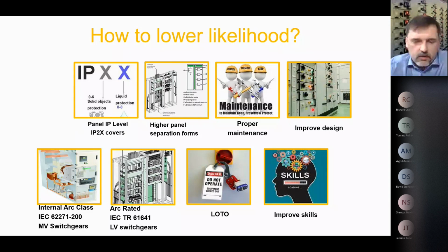You might improve your design. And by improved design, I mean the design of your system. So when you are in the design phase, of course, not every configuration of your system is effective, especially for safety. So you might work with this a bit more. But as well as a hardware design of the panel itself. For the panels, when we talk about the switchgears, we might have internal arc classified switchgear for medium voltage systems under IEC 62271-200 for the IEC world, but there's also the ANSI C37 standard for it.